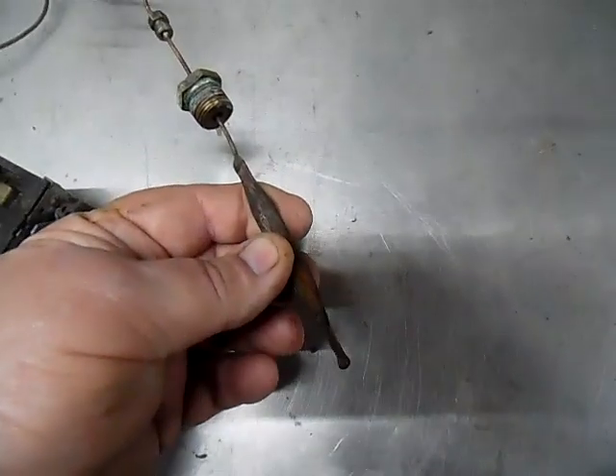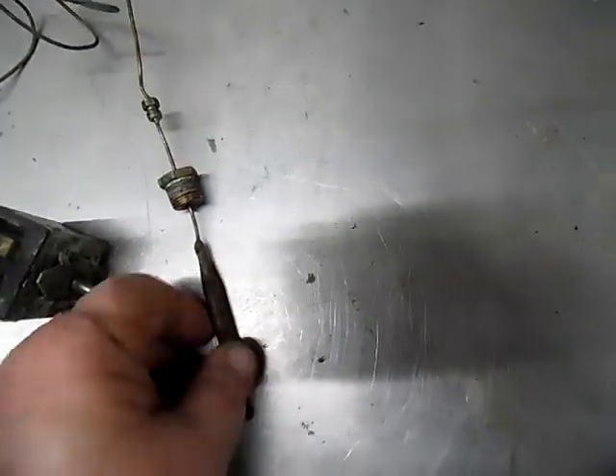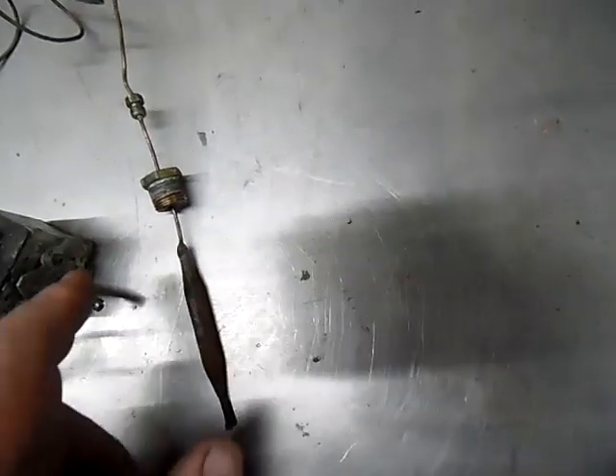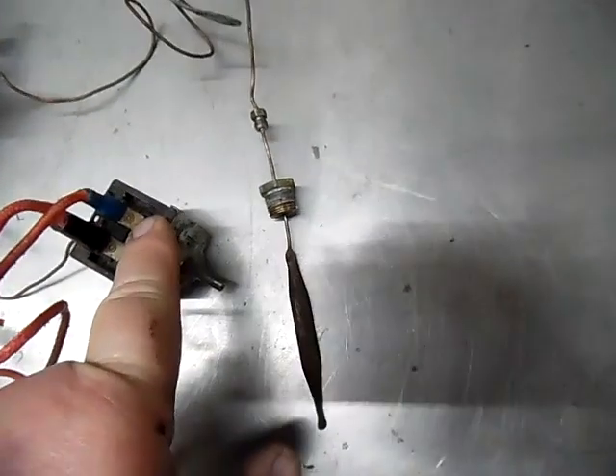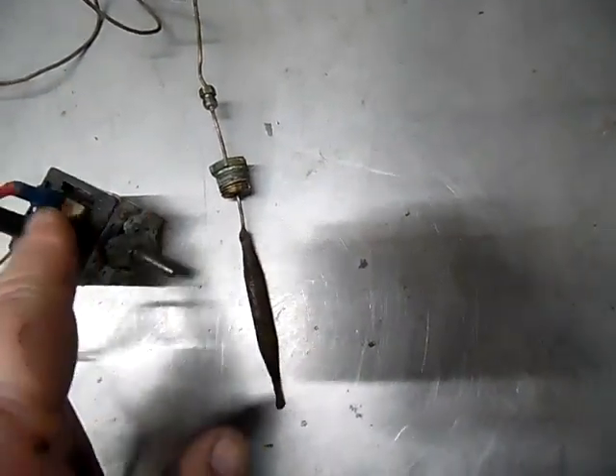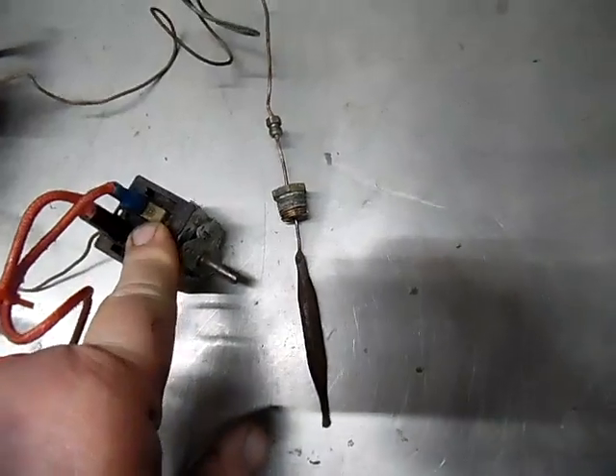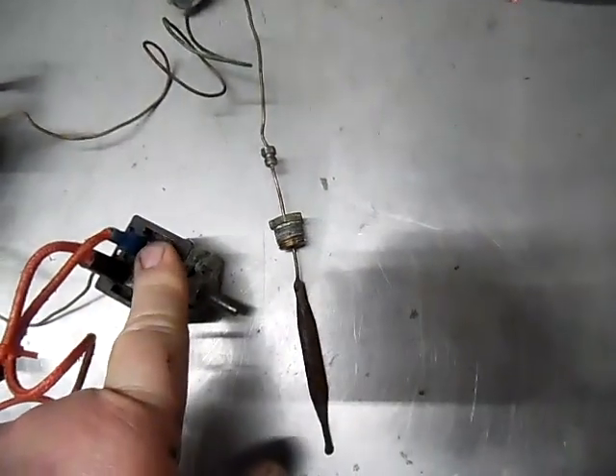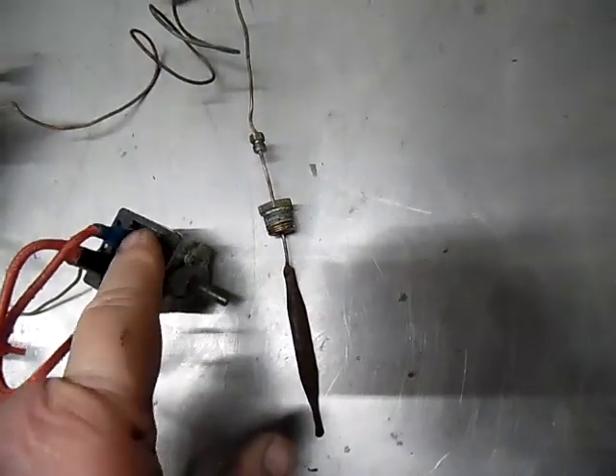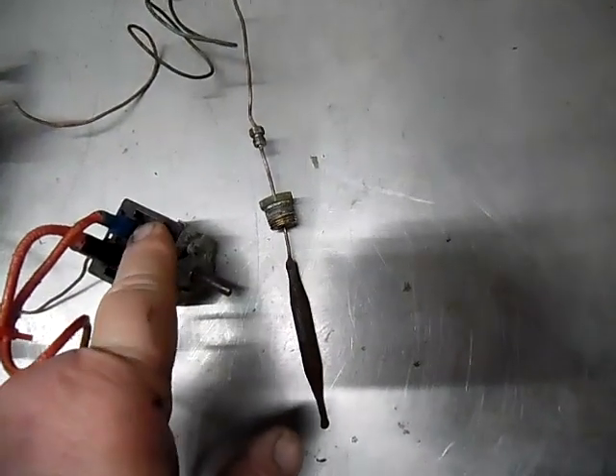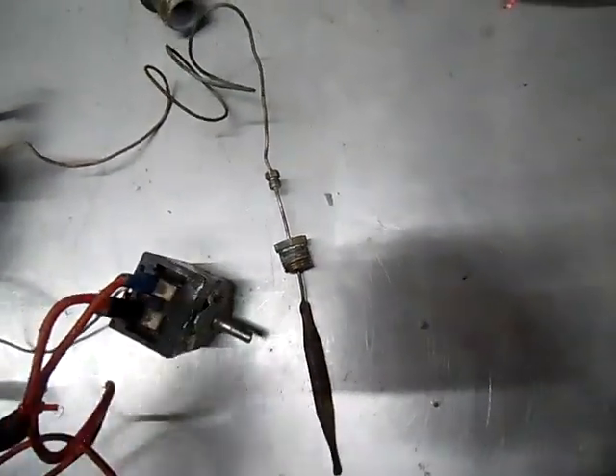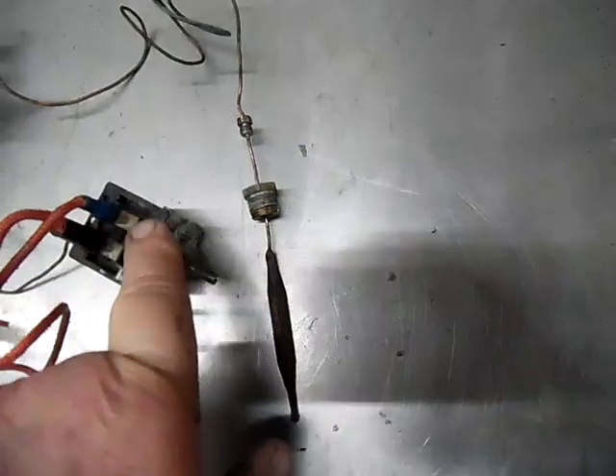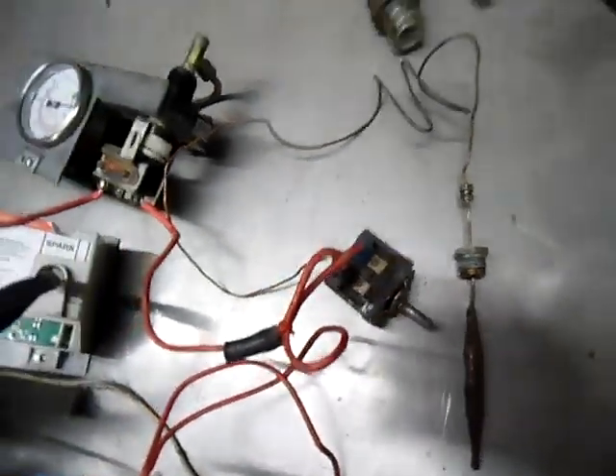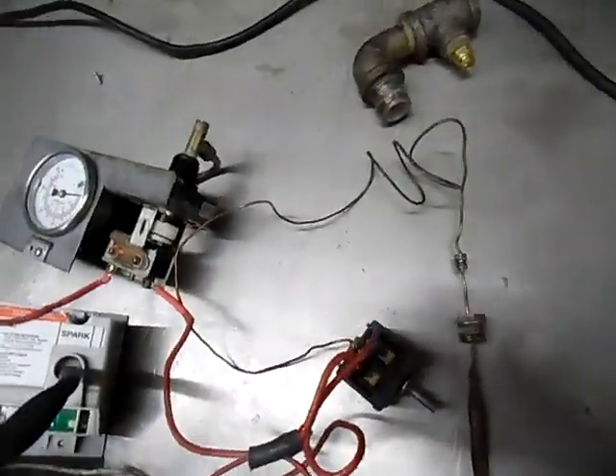It goes into your water jacket, and so let's say you turn it halfway down and it gets to 125 degrees, and this switch will cut out. If you have this all the way at hot and this cuts out at 100 degrees, 150 degrees and not 300, then most likely your thermostat. But again, check your power. If your power cuts out here, then you know this shut off here. You got power from this one, you know, okay, it's reading the thermostat. Thermostat cut off too soon. So then you go replace the thermostat.